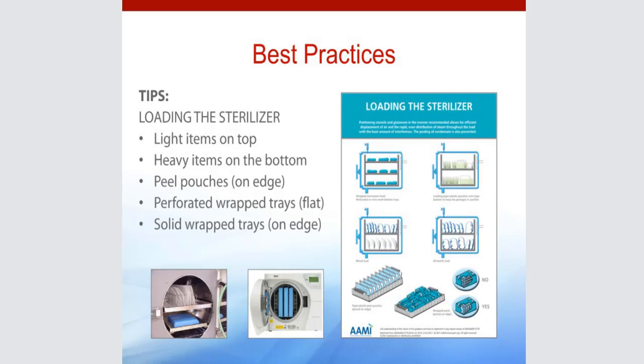If you are an office that chooses to do and maintain common practice and you're going to stay with horizontal loading, you need to follow your sterilizer manufacturer's instructions for use. The vast majority of the sterilizer manufacturers are now saying paper side down and plastic side up. There is one manufacturer that is still saying paper side up. If you are loading horizontally, they have to be in a single layer. They should not be overlapped or touching.